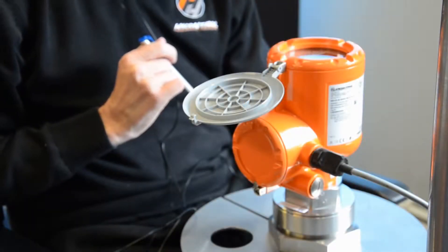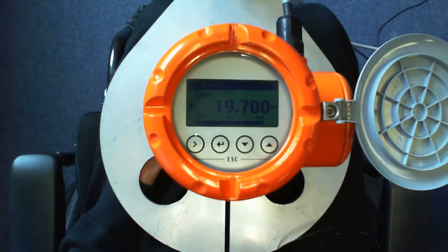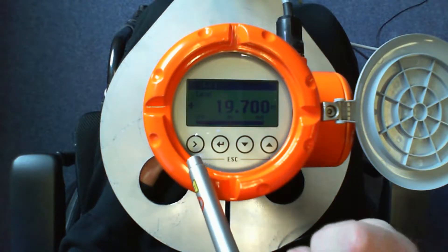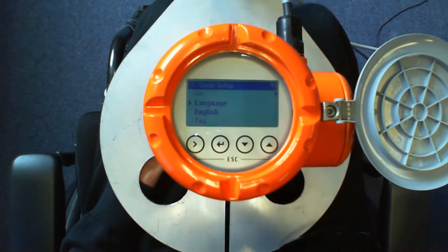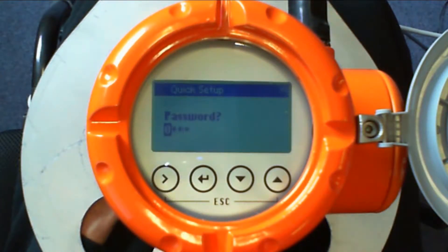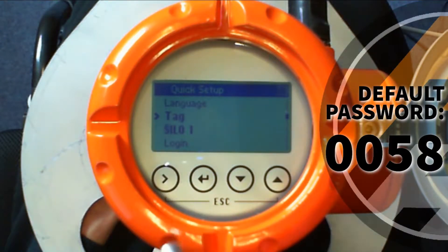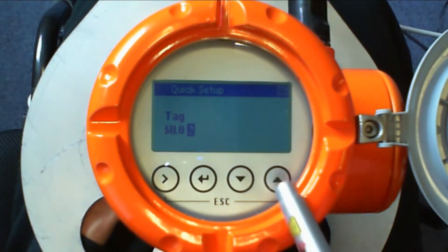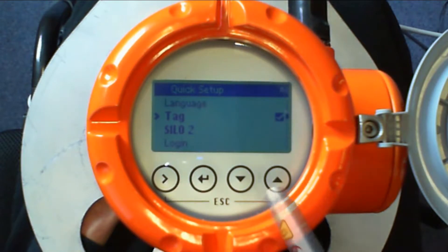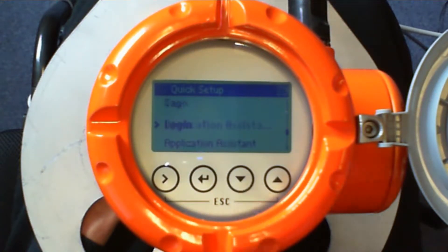We're going to set the radar up for level measurement in feet and go through all of the programming needed to do this. Initially when you power the device up it will be in metric measurement with a 20 meter range. Go into the parameters, then into the quick setup menu. First, we need to give the application a name — this device is on Silo 2. Enter the password, which is 0058, and we can now change our tag name to Silo 2. With the quick setup we can now go to the application assistant and select a standard setup.